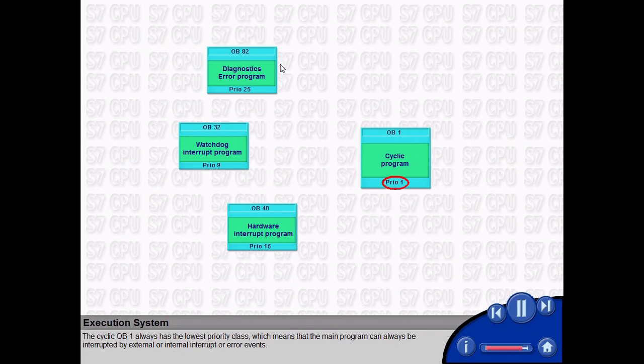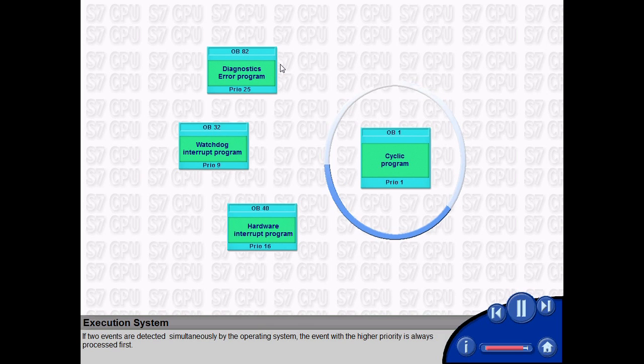The cyclic OB1 always has the lowest priority class, which means that the main program can always be interrupted by external or internal interrupt or error events. If two events are detected simultaneously by the operating system, the event with the higher priority is always processed first.